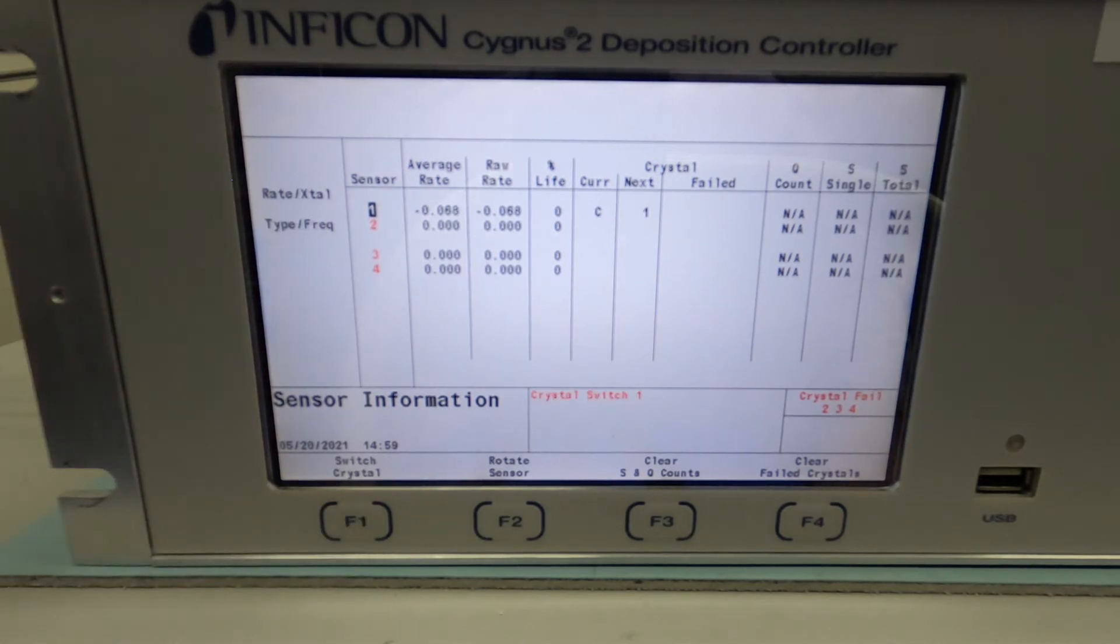The crystal position 12 is displayed as the assumed current position until the changeout is complete and a rotate head or crystal switch function is performed. At the end of the rotate head function, the sensor will be at position number 1.